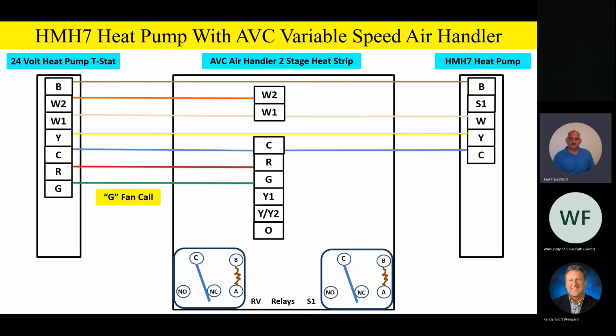And G is our fan call. So all of this wiring is going to look real familiar to you. It's basically the same as everything else. And please note something too, that when you take a look at that outdoor unit, we're only going to still have 5 wires outside. Even on a high-end variable speed product, we're still only going to have 5 wires outside. And I think that's really cool myself.